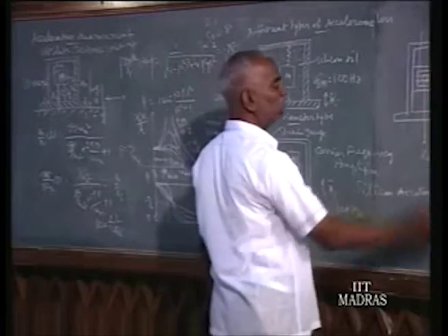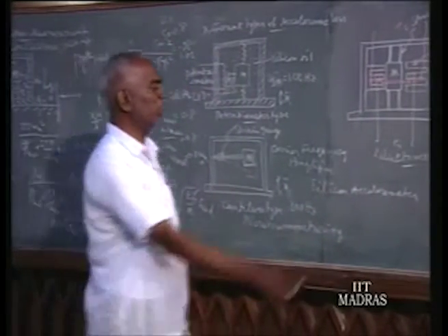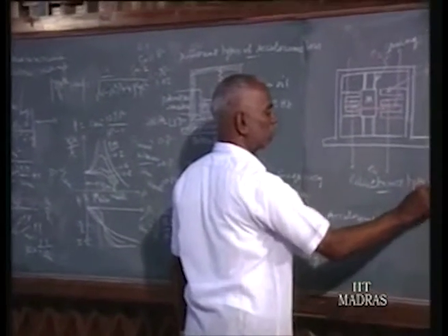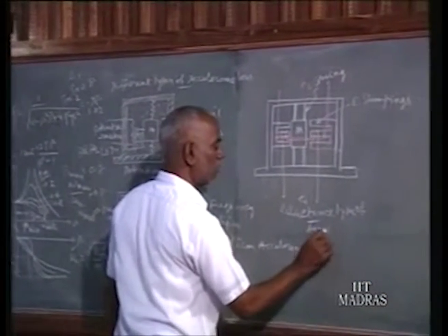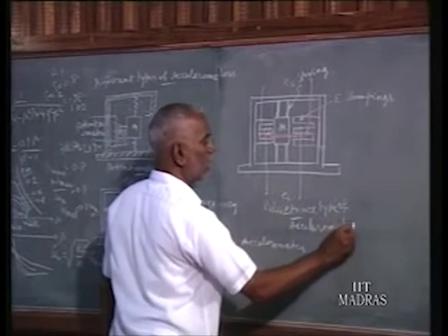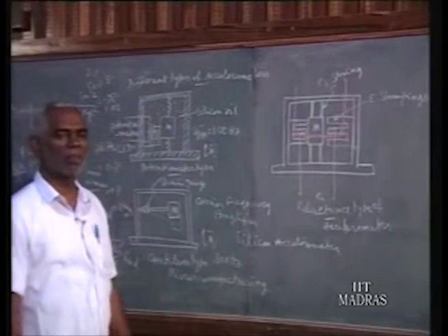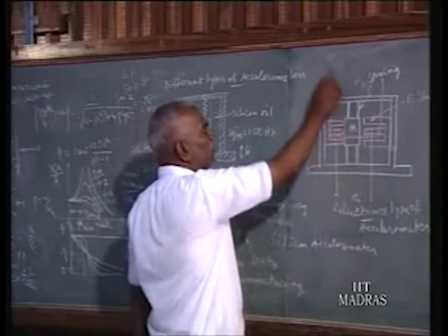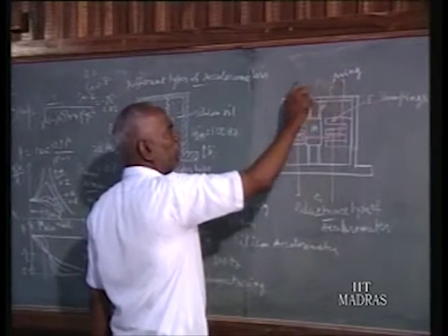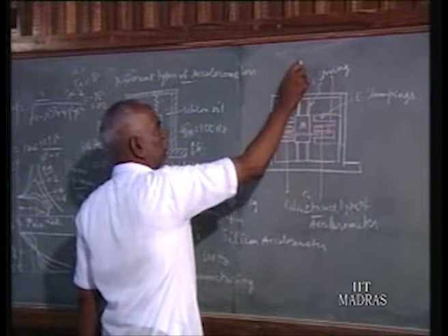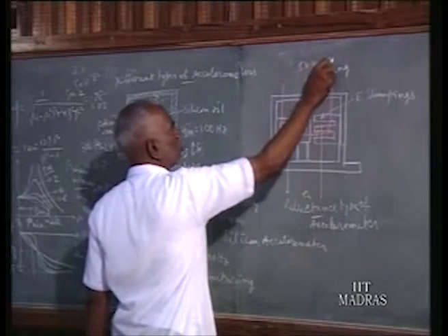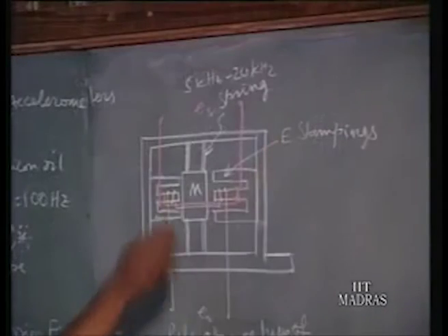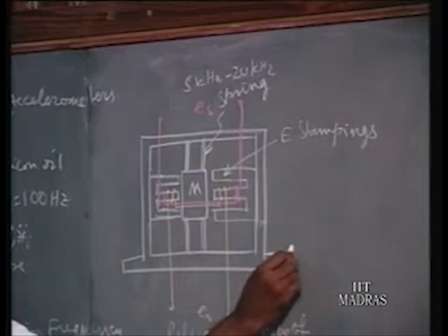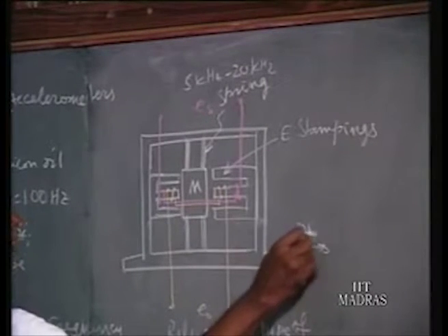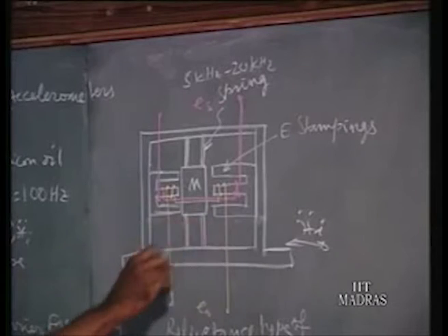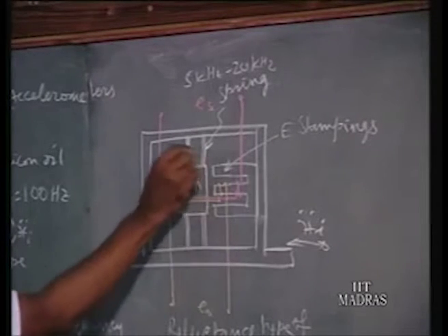And another type makes use of the reluctance principle. This is the reluctance type of accelerometer. It makes use of the resistance to the flow of magnetic lines. The magnetic lines are created by the excitation winding, with a frequency that can vary from 5 kilohertz to 20 kilohertz. This is the direction of motion for this xi2 dot. This mass is here, and it is supported by 4 leaf springs.